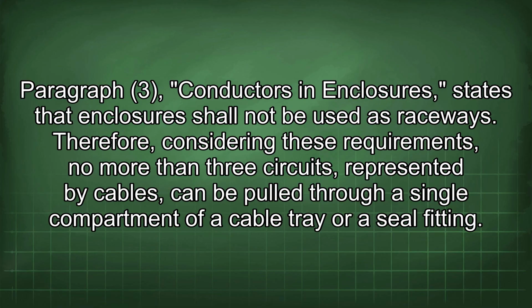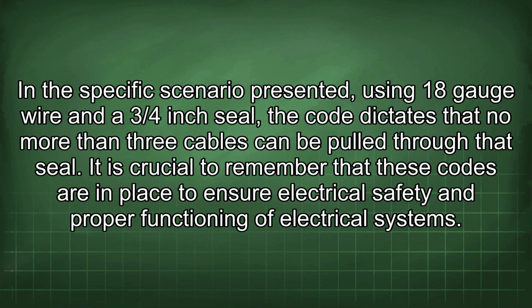Therefore, considering these requirements, no more than 3 circuits, represented by cables, can be pulled through a single compartment of a cable tray or a seal fitting. In a specific scenario presented, using 18-gauge wire and a 3/4-inch seal, the code dictates that no more than 3 cables can be pulled through that seal.